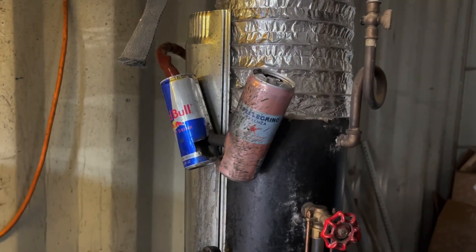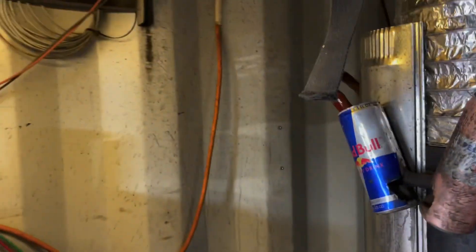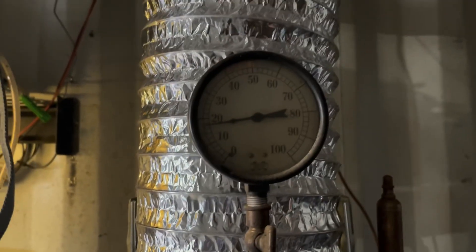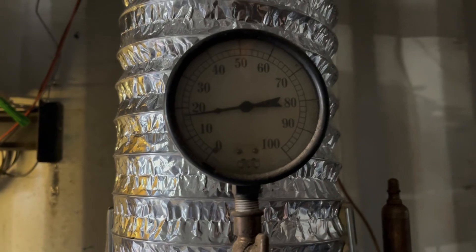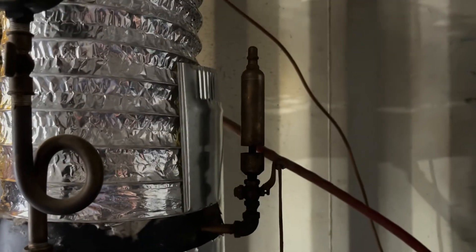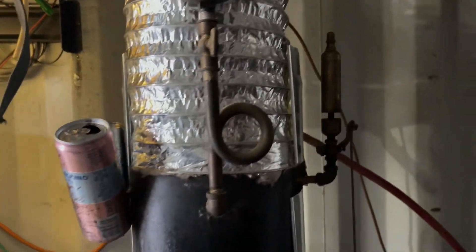I tested the pop-off valves today. I'm sure some people who run steam are going to be really annoyed in me doing this, but I had these loosely put on there because, as you can tell, they kind of spatter a bit if they haven't run in a while. Even with these cans on there, it's spattered over there. We've got about 20 pounds, probably 18 pounds on the boiler. Tiny little whistle doesn't really make a great sound. My other whistle makes a bunch better sound.